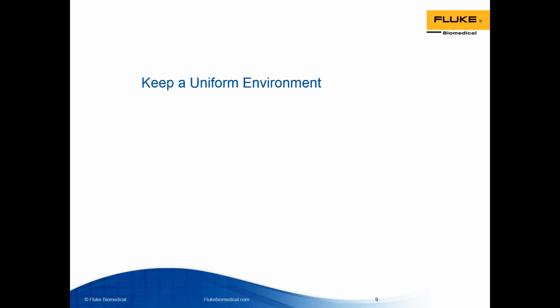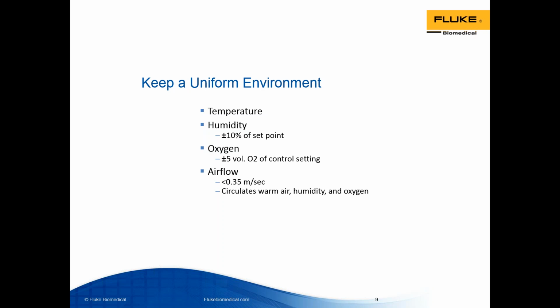Once the incubator achieves STC, its most important function then is to keep a uniform environment in all parts of the chamber. So temperature should be the same in all parts of the cabinet. Humidity and oxygen should be at appropriate levels and stay constant. The airflow right above the mattress shouldn't exceed 0.35 meters per second. And it should stay relatively constant to really help circulate that warm temperature, the humidity and the oxygen, to ensure that all parameters are consistent throughout the cabinet.